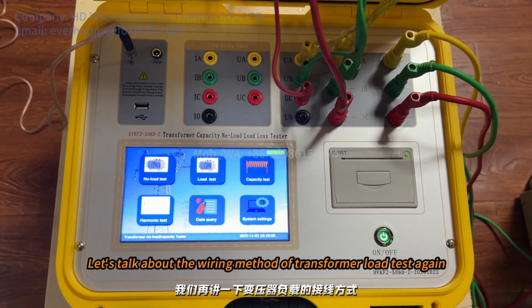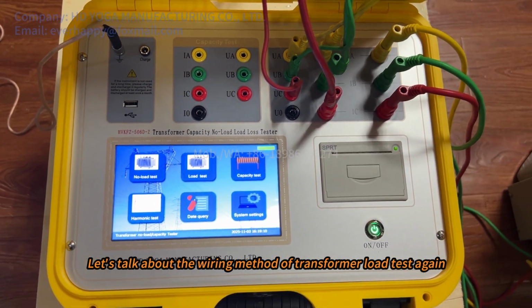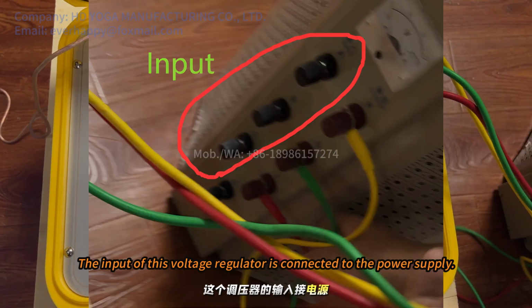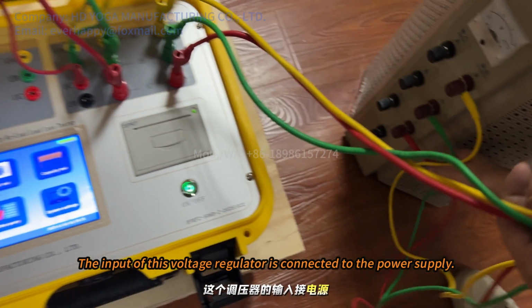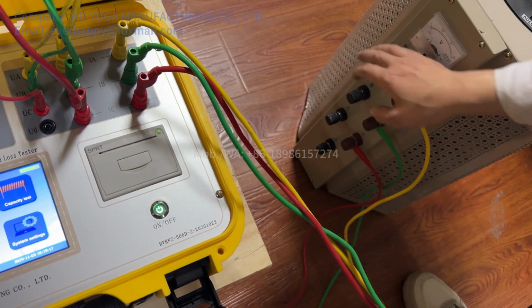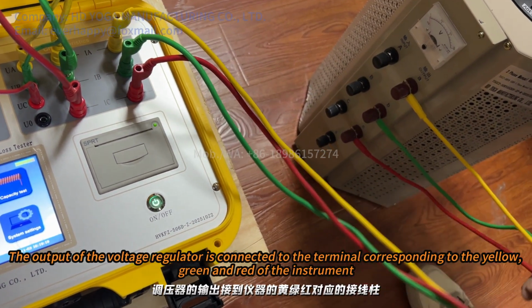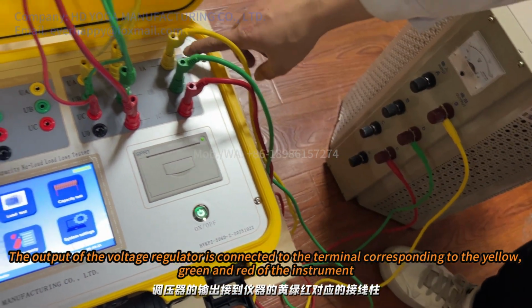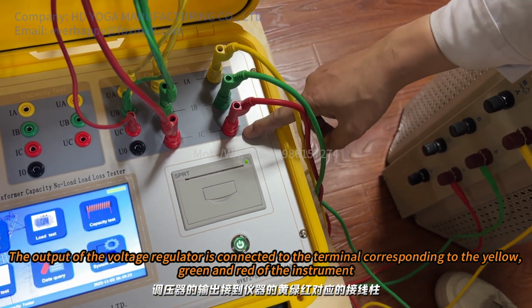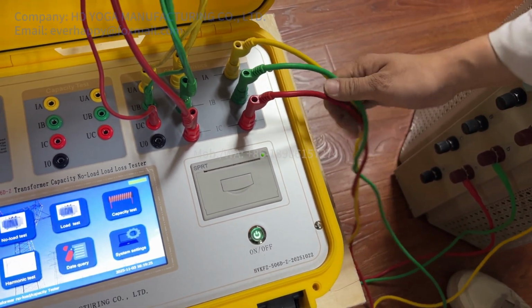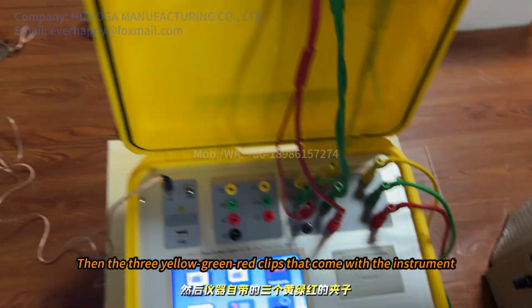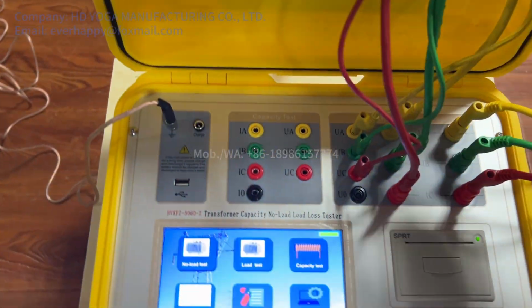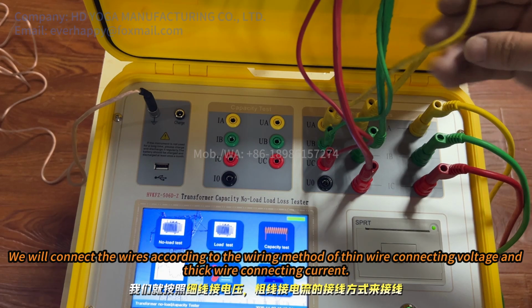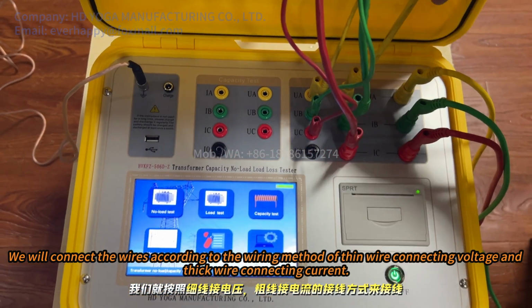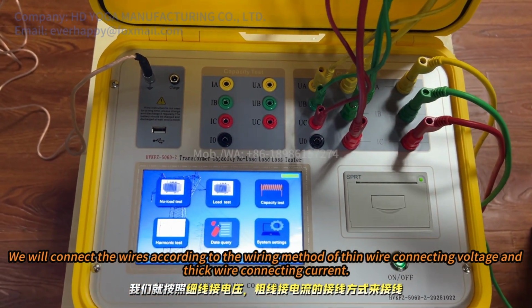Let's talk about the wiring method of the transformer load test again. Same as before, first the input of this voltage regulator is connected to the power supply. The output of the voltage regulator is connected to the terminals corresponding to the yellow, green and red of the instrument. Then take the 3 yellow, green, red clips that come with the instrument. We will connect the wires according to the wiring method of thin wire connecting voltage and thick wire connecting current.